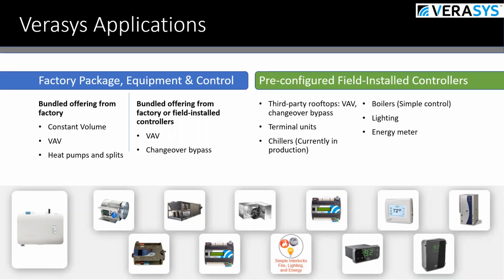In the beginning, Verasys required something in between the Smart Building Hub and a third-party unit like a Trane, Carrier, Lennox, or a thermostat, because it couldn't communicate otherwise. But now you can have fan coils or VAV boxes set up on a Verasys zone coordinator, and then have a Trane rooftop that's BACnet MSTP, and you can pull it right in.